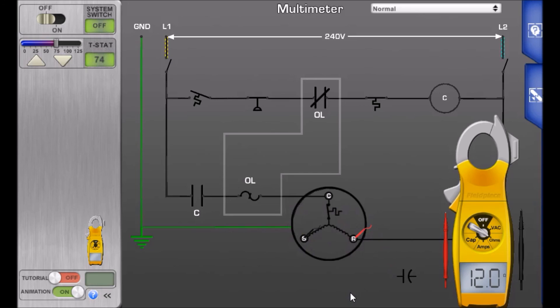Now the different compressors will have different resistance measurements but the total between common and start and common and run, if you total those up that's what you should be measuring between start and run windings. And if you measure anything over 20 ohms on any leg you probably have a bad compressor but this one happened to check out good. So the next one we'll look at is an open winding in the compressor.